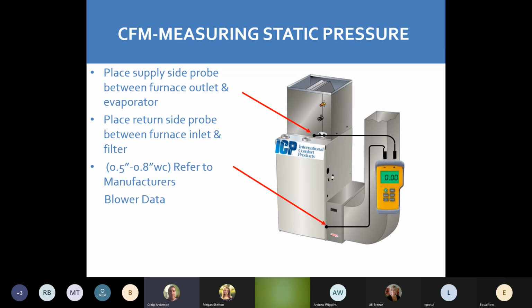So if the motor is overheating and slowing down, we can get improper airflow going through that coil and we can get freezing. If we don't have any static on the motor, then the motor is always searching, because it's trying to hit a static pressure. So it could be revving up, slowing down, revving up, slowing down. So static pressure is a big thing.